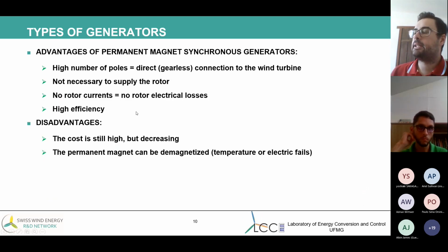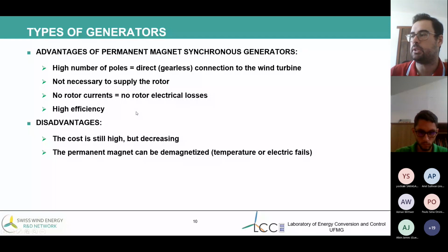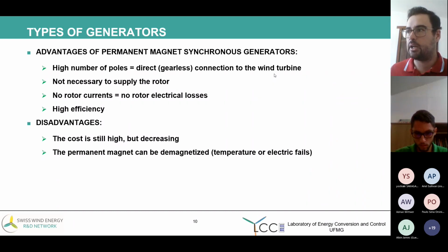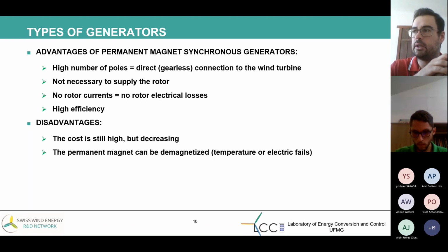Advantages of the permanent magnet synchronous generator. It's one of the main technologies in expansion worldwide. The high number of poles permits the direct connection to the wind turbine, so it's gearless. What does a gearless system mean? One less component. We don't have the gearbox, a component with mechanical fragilities that needs constant maintenance. If we avoid the gearbox, it's very good.